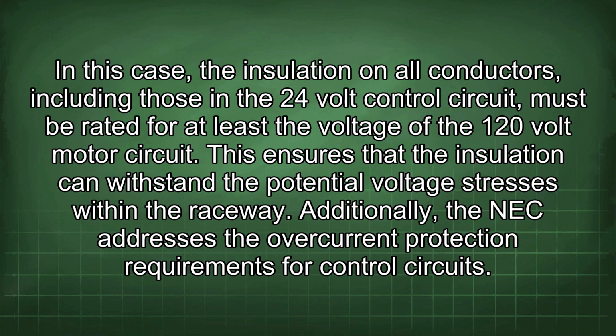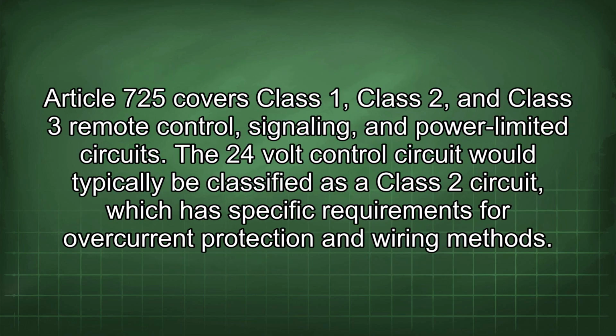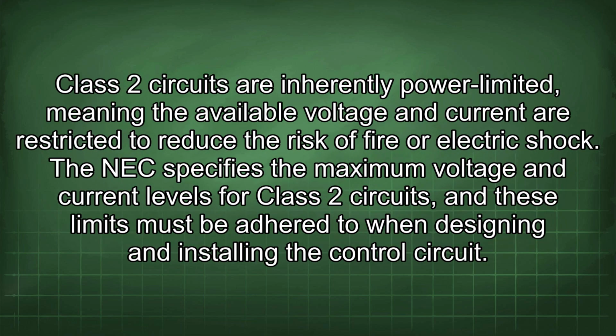Additionally, the NEC addresses the overcurrent protection requirements for control circuits. Article 725 covers Class 1, Class 2, and Class 3 remote control, signaling, and power-limited circuits. The 24-volt control circuit would typically be classified as a Class 2 circuit, which has specific requirements for overcurrent protection and wiring methods. Class 2 circuits are inherently power-limited, meaning the available voltage and current are restricted to reduce the risk of fire or electric shock. The NEC specifies the maximum voltage and current levels for Class 2 circuits, and these limits must be adhered to when designing and installing the control circuit.